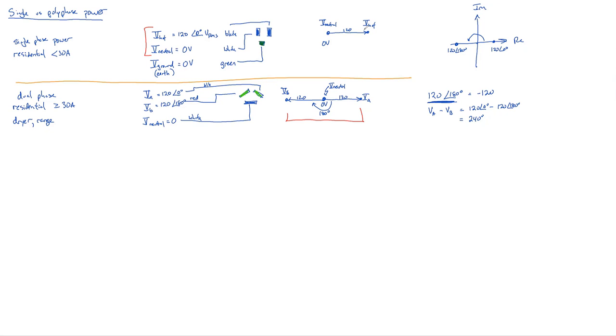Now, something I think is really interesting is that houses are meant to have balanced loads. The amount of load on your VA leg should be about the same as the amount on your VB leg. That means half of your house is divided into two parts: half is powered by VA and neutral, and the other half by VB and neutral. Within a single room, it's always powered by the same leg, VA or VB, but different rooms on different sides are probably powered by different legs.